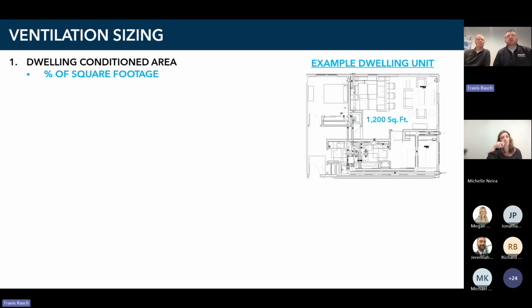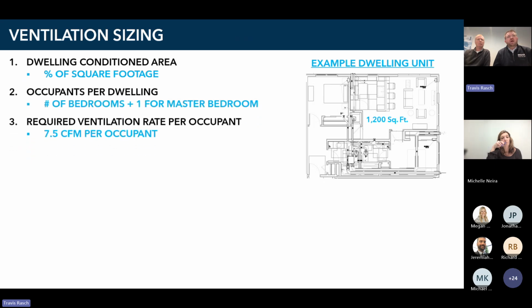The ventilation rate is going to be dependent on basically 3 key things. The first is the square footage of that dwelling. Again, in this example, we've got a 1,200 square foot apartment. The second is the number of bedrooms. What that number of bedrooms is going to dictate is the occupants within that dwelling. There's an assumption within the ASHRAE calculation that there are 2 occupants in a master bedroom. And then finally, ASHRAE has determined for our overall indoor air quality that 7.5 CFM of continuous ventilation is required per occupant. And there are 2 ways this number can be determined.